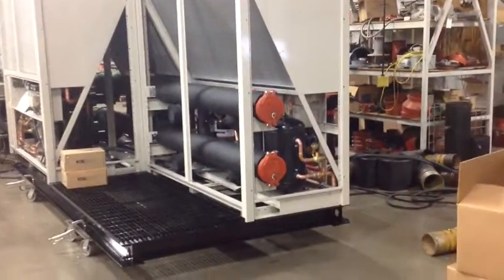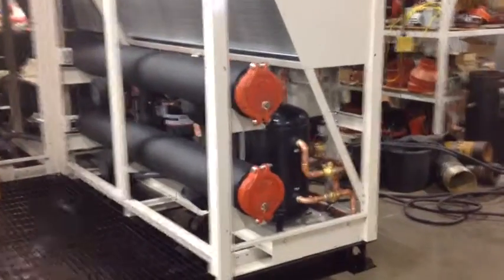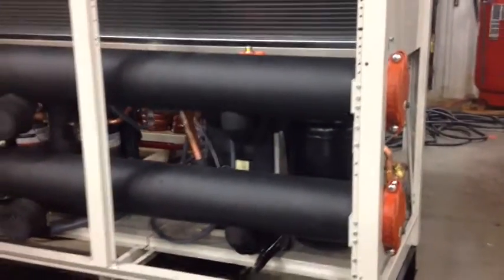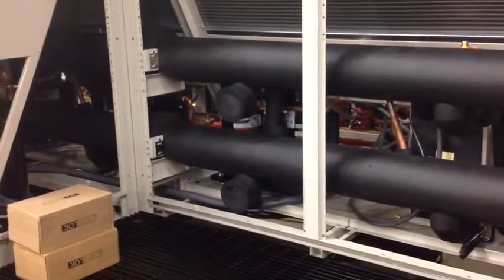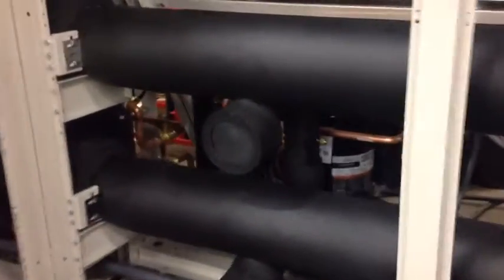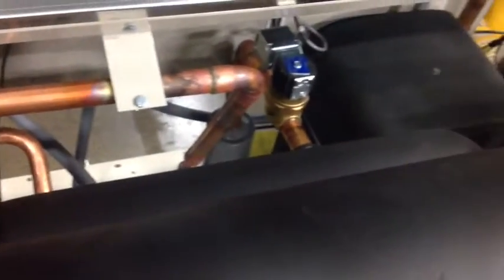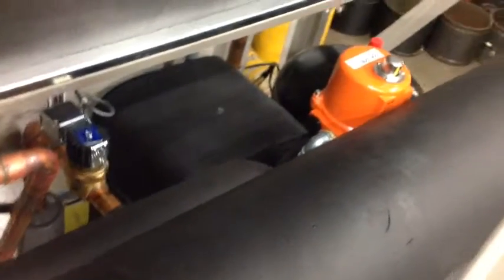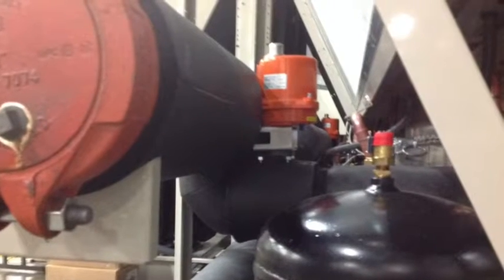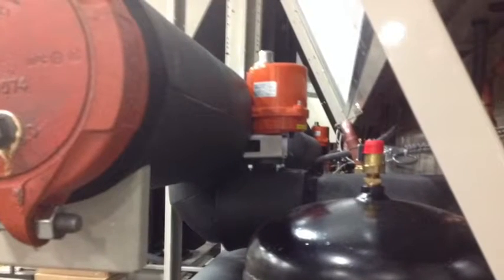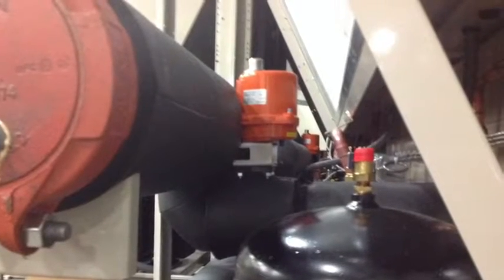As we look into the 3 mechanical module array, we'll note that the water headers are only present on one side of the unit. This is the building side of the unit. The upper header is entering chilled water and the lower header is leaving chilled water. This gives us counterflow in the evaporator, with refrigerant moving up as it evaporates and chilled water flowing from the top down. We see the 2 compressors and the tandem refrigeration set for the single refrigerant circuit in our module. Moving to the right, we see the evaporator, the variable flow valve, and the receiver. In this still shot, you can see the Belimo actuators of the variable flow valves in both of the modules on the building side of the array.